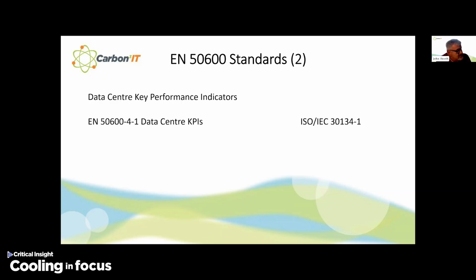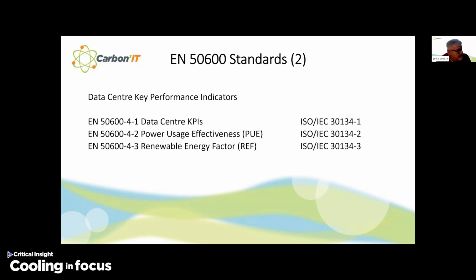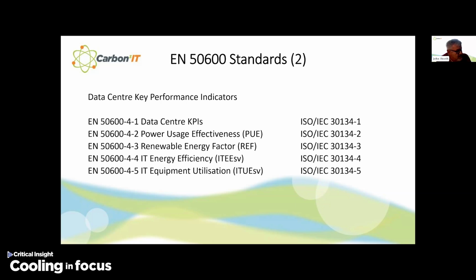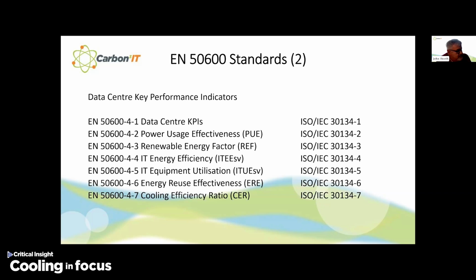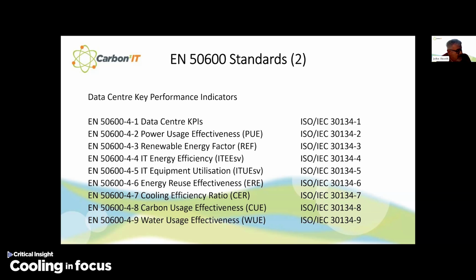We also have the data center KPIs, and these are the ones that are asked for by the Commission. So we've got PUE, renewable energy factor, IT energy efficiency, IT equipment utilization, energy reuse effectiveness, cooling efficiency ratio, carbon usage effectiveness, and water usage effectiveness. Now, of those, there's only three that you need to worry about for compliance reporting: the renewable energy factor, your energy reuse effectiveness, and your water usage effectiveness.